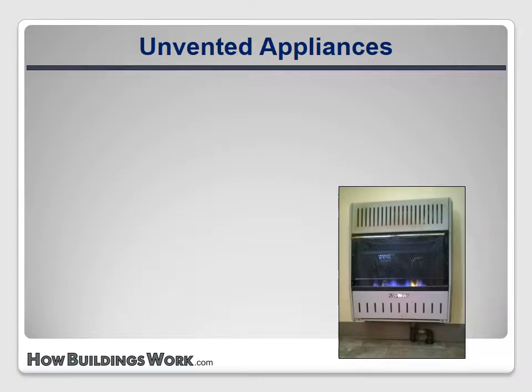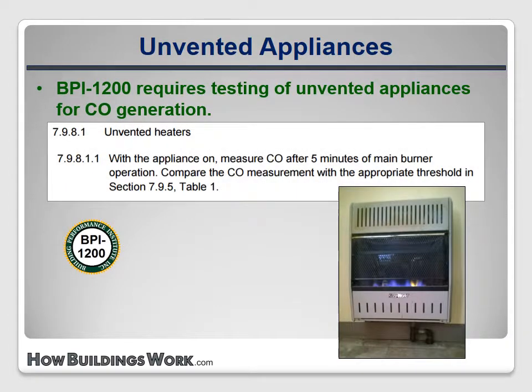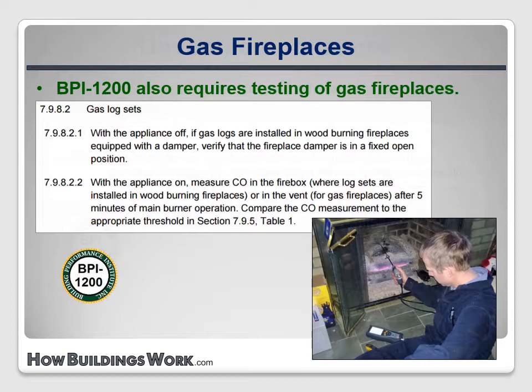While the BA Standard simply requires that no unvented appliances operate in the living space, BPI 1200 requires testing of these appliances to determine if they require repair or removal. BPI 1200 also requires that gas fireplaces be tested for carbon monoxide generation — including both fireplaces manufactured to burn gas and wood fireplaces with a gas log set installed. For these fireplaces, as well as for unvented heaters, testing is to be done after five minutes of operation.